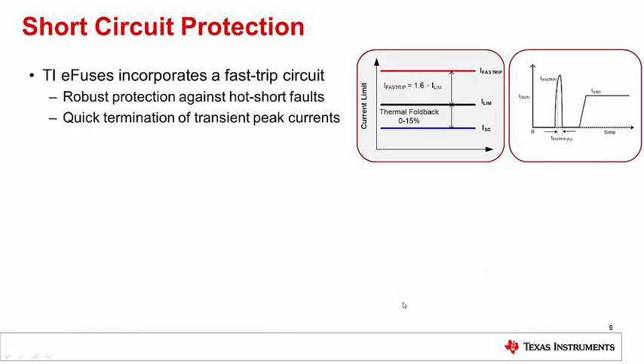One of the advantages of eFuse over discrete solutions is the ability to respond faster for short circuit faults. During a transient short circuit event, the current through the eFuse increases very rapidly. The current limiter amplifier of the eFuse cannot respond very quickly due to its limited bandwidth. To solve this, TI eFuses incorporate a fast trip current comparator, which shuts down the FET very quickly when the load current Iout exceeds the fast trip current threshold I fast trip. The fast trip threshold is set at 60% higher than the programmed overload current limit.